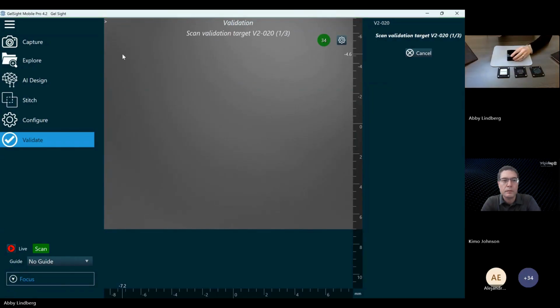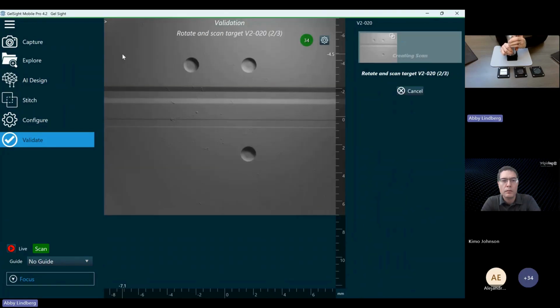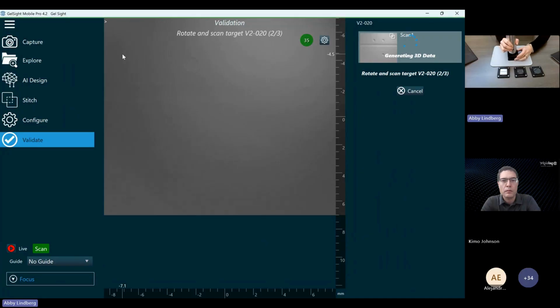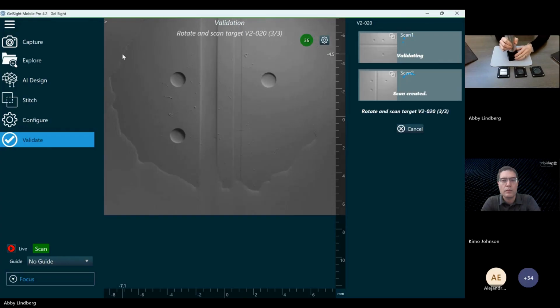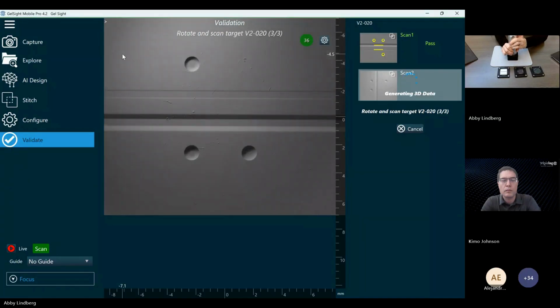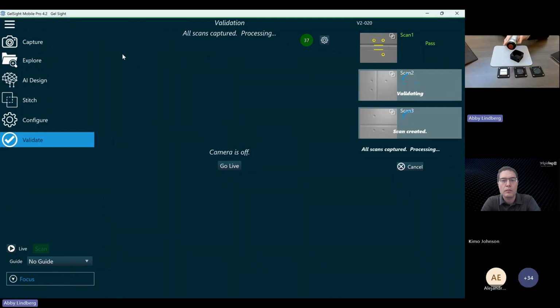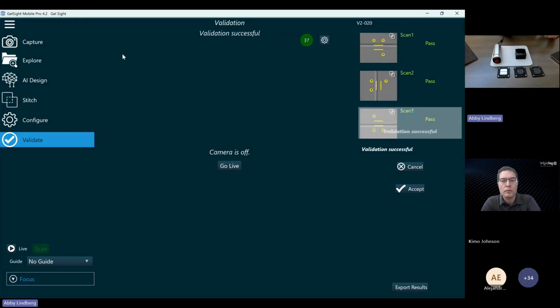I'll take our fixture and snap it on the front there. And I'll align our system in here. And we'll press down and take the scan. And I'm going to rotate it and go ahead and take the next scan. And we'll go ahead and take a third scan as well. So 3 scans involved in the validation process, and we're rotating it so that we have to check all of those dimensions across multiple orientations and multiple scans. So we're not just checking one time for one measurement in one location.